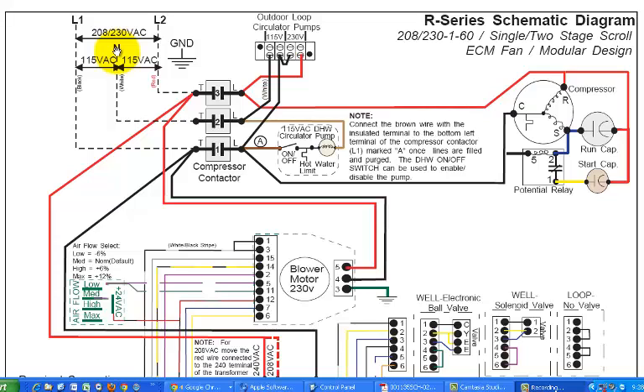What the neutral wire does is it splits the legs, the L1 and the L2, in half effectively. And so if we were to measure between the neutral wire, which will typically be a white wire, the lines feeding L1 and L2 are almost certainly going to be black and red. The order doesn't matter. It could be red on L1 and black on L2 or vice versa. It really makes no difference at all because you're seeing the 240 volts between them. And then again, between the neutral wire and either one of the lines, we're going to see 115 volts showing up.